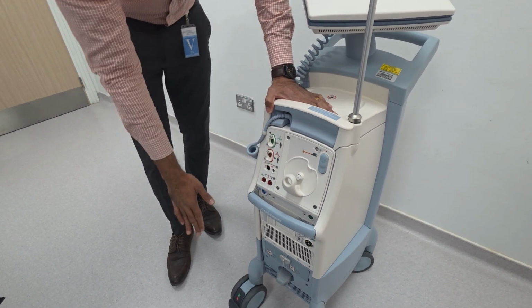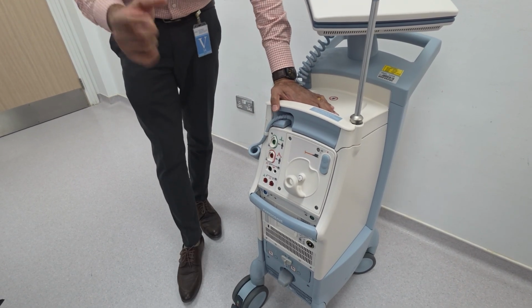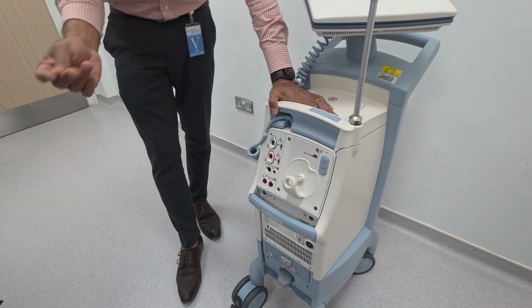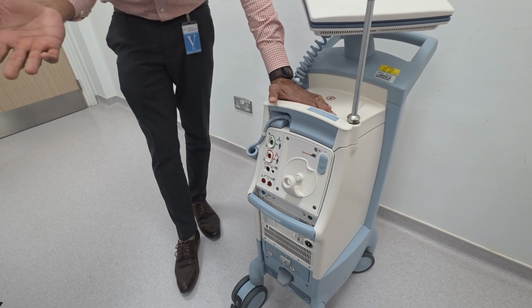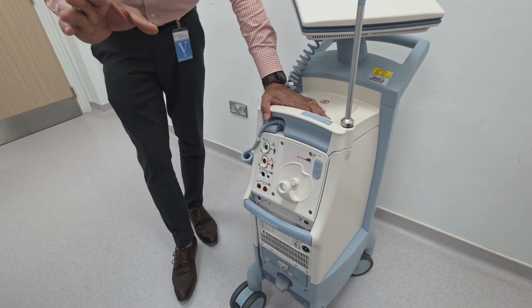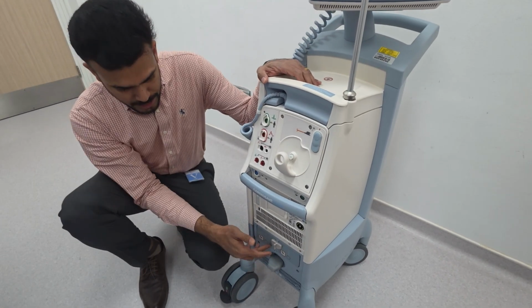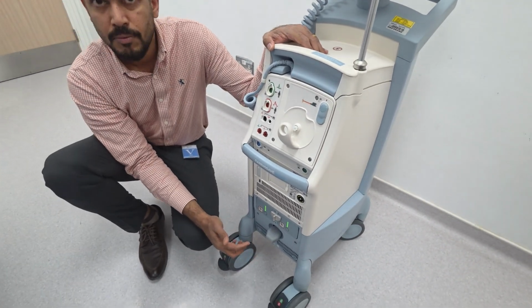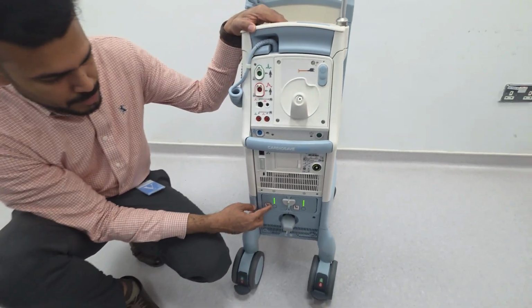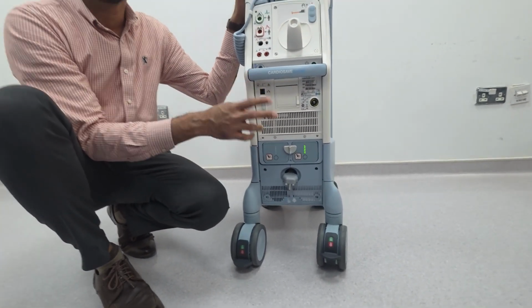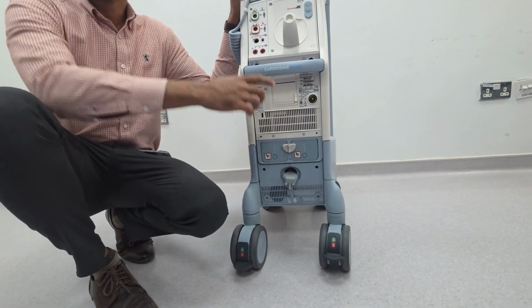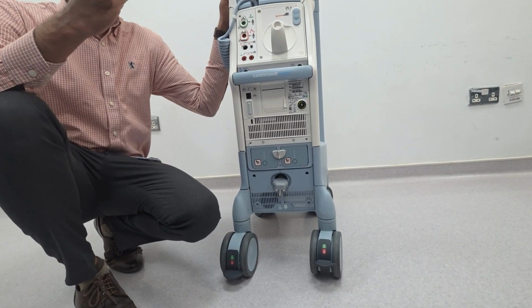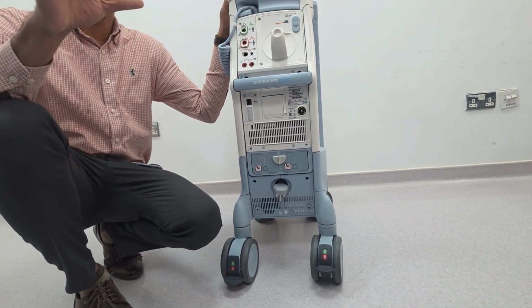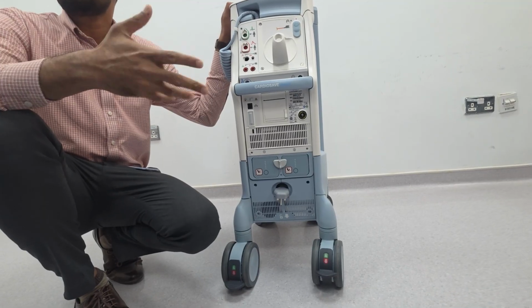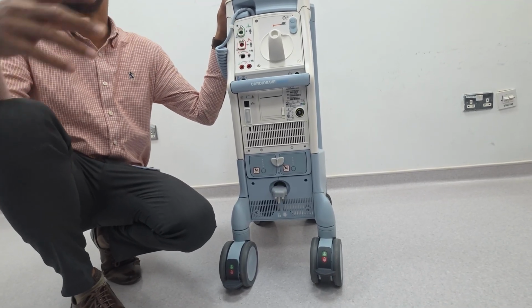And the major difference from CS300 is we are using lithium-ion batteries. Okay, in the CS300 you don't have access to the batteries, but here the end user can change the batteries. We are using lithium-ion. You can see the capacity of the battery without even switching on the machine. By pressing, each LED is indicating 20%. So 5 means 100%. For one full battery, it will work around 90 minutes if the patient heart rate is 90. Okay, so in total you will get 3 hours for transportation.